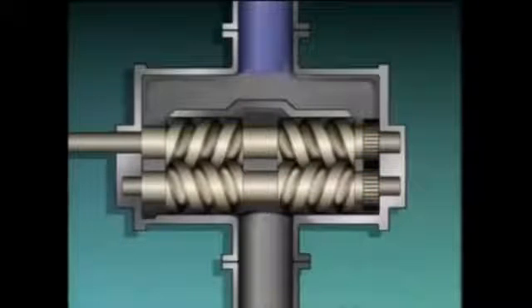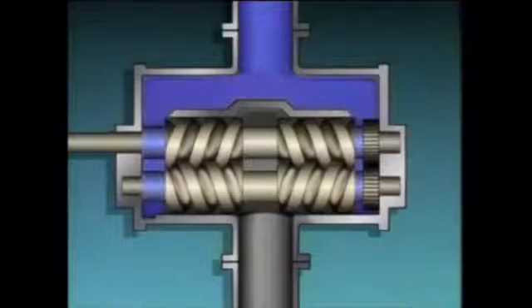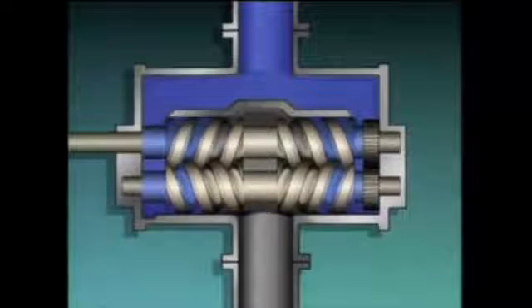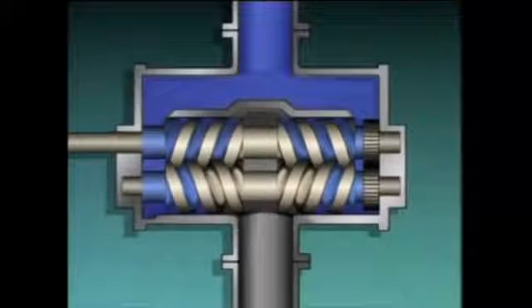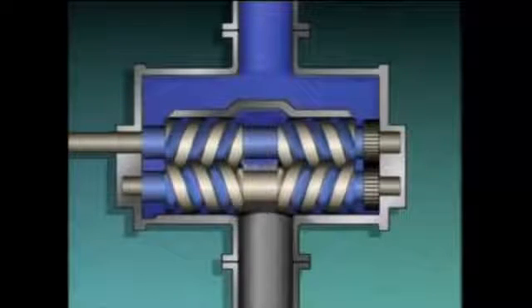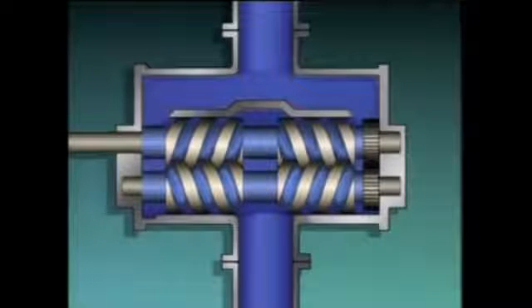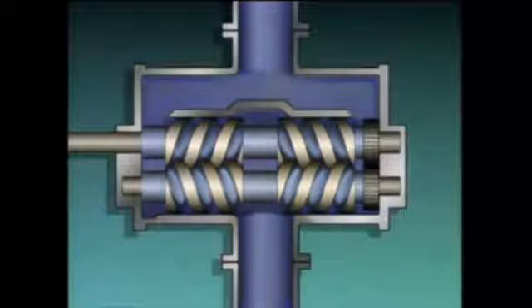During operation, process liquid enters the suction of the pump and is directed toward both ends of the casing. As the screws rotate, the liquid becomes trapped between the casing and the screws. The liquid is moved from both ends of the pump toward the center, which is also the discharge of the pump. The force exerted by the screws pushes the liquid out of the pump and through the discharge piping.